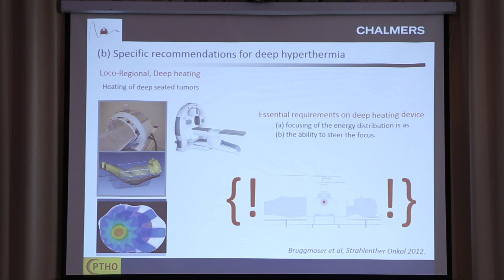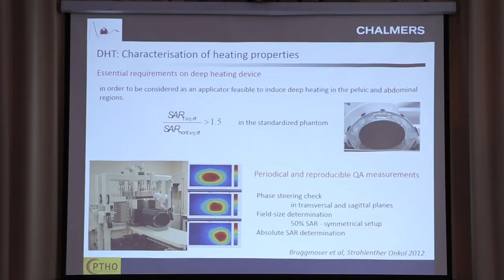For the characterization, we require the focusing. That means that if we again have a standardized phantom, then we require that the SAR ratio of absorbed energy in the target to the non-target should be more than 1.5. And this phantom also serves for periodical and reproducible QA measurements, so for phase steering checks and field size determination, etc.